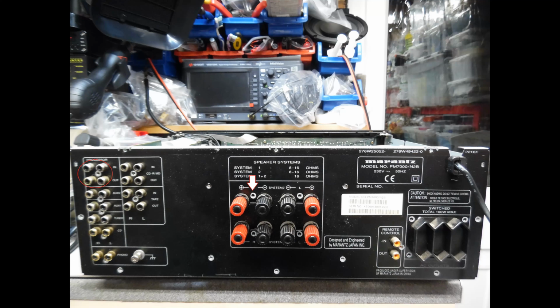The other thing I want to highlight, shown here via the arrow, is that when you disassemble the amplifier, it uses a common ground connection throughout. So you'll not see any painted surface over those screw holes, and that's done deliberately.